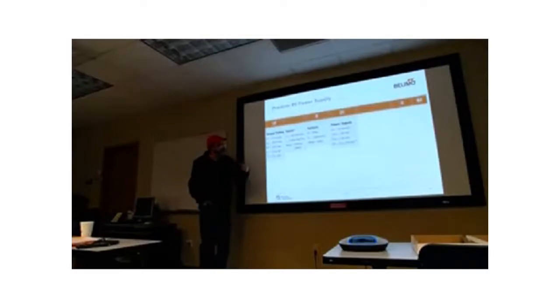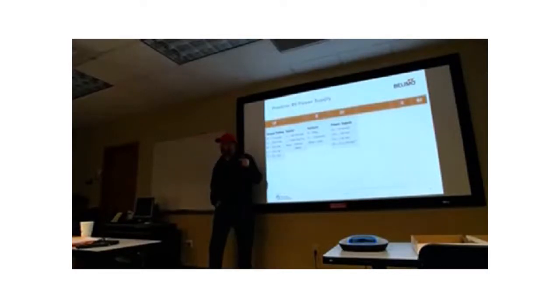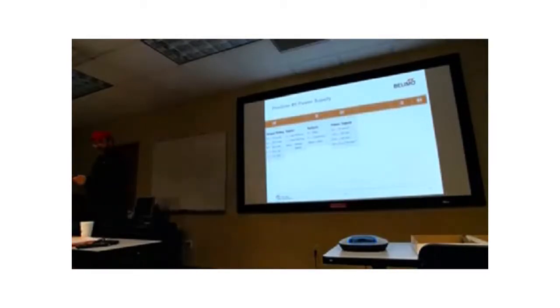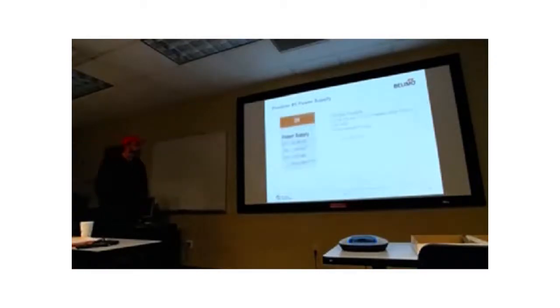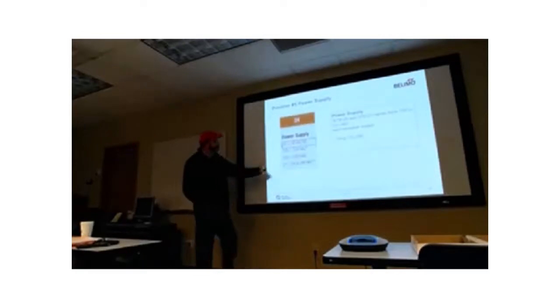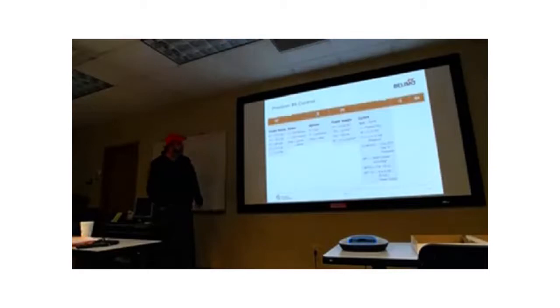It's all 24 volts AC for the most part. What happens is the actuator converts that to DC. When it comes in, it goes through rectification, for the electricians in the bunch here. But you can provide either AC or DC voltage to these things. It also goes 24 to 125 volts DC, although nobody really ever uses that, I don't think.